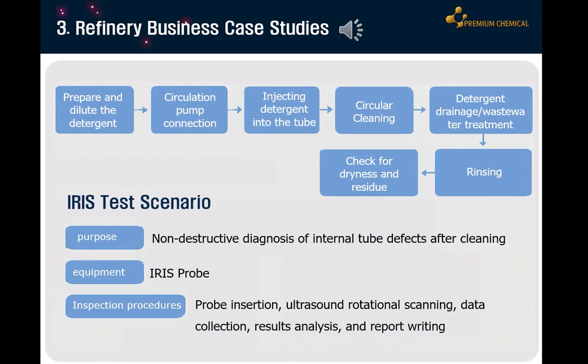The chemical cleaning process involves: 1. Dilute the prepared cleaning agent with water. 2. Connect the air fin cooler to the circulation pump using a high-pressure hose. 3. Operate the circulation pump to inject the cleaning agent into the tube. 4. Operate the pump for a specified period of time to perform the circulating cleaning. 5. Once the process is complete, drain the cleaning agent from the air fin cooler for wastewater treatment. 6. Continue rinsing with clean water.